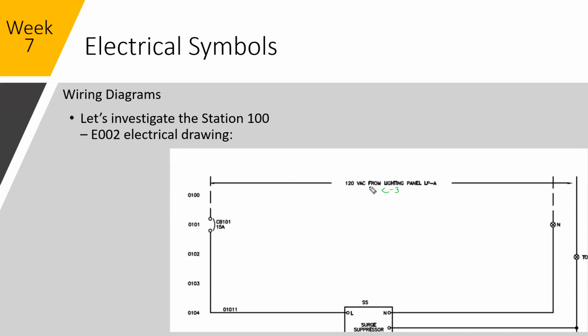It's always nice for the electrician to know which breaker they need to turn off to turn power off to the panel. We've got 120 volts, typically line, coming in here into the circuit breaker. We've got N here for neutral. For 120 volts, you'll have a hot or a line and a neutral. And over here, this is ground. You could have somewhere on here, it should indicate ground.